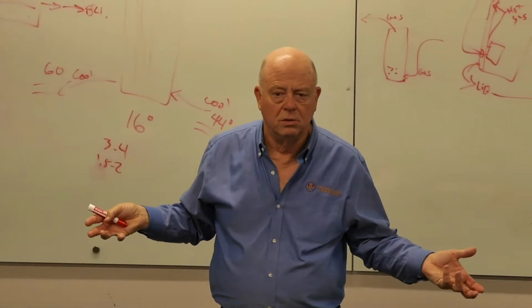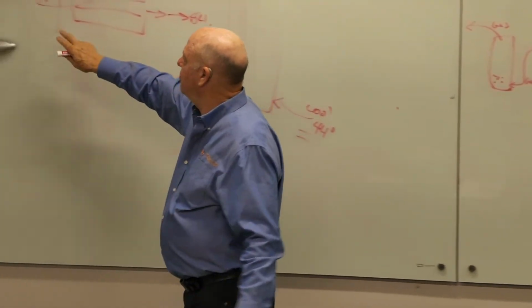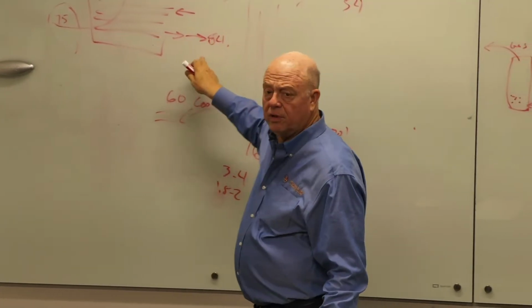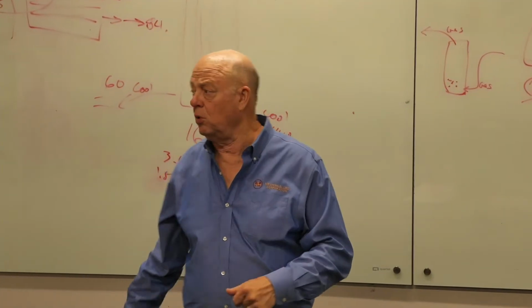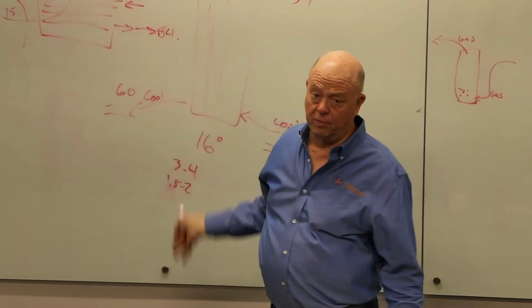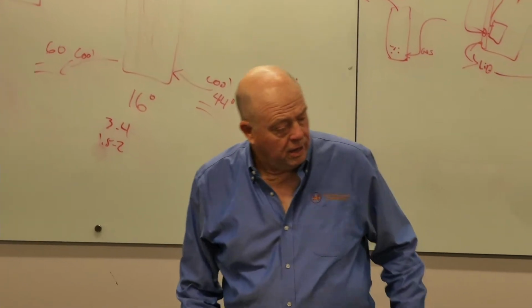Even a swamp cooler works with an approach. And it's a function of the wet bulb against whatever the leaving air temperature is coming out of the device, or in this case, the leaving water temperature from our heat exchanger. Okay.